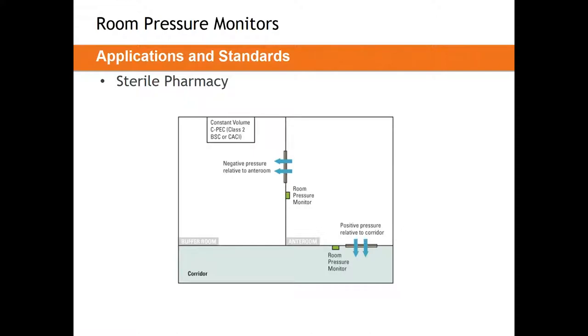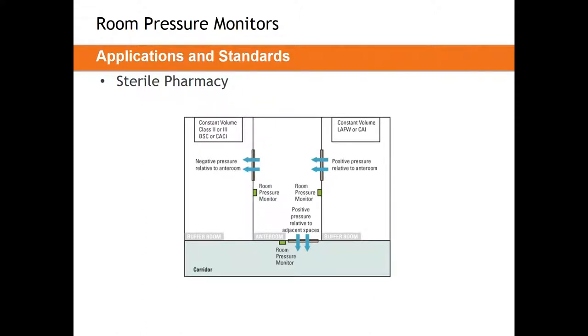You do have the option of measuring from the corridor to the anteroom and from the corridor directly to the buffer room. This is a little bit more stable and helps diagnose problems — wherever an issue occurs, whether a motor has failed or controls are over-tuning, you can directly identify which room it's happening in. The downside is that the pressures in the standards (0.01 to 0.03 or positive 0.02) aren't directly what you'll measure; you have to infer the correct pressure, making it a little harder for facility staff.